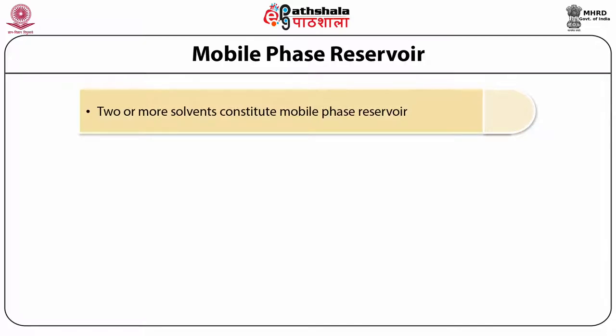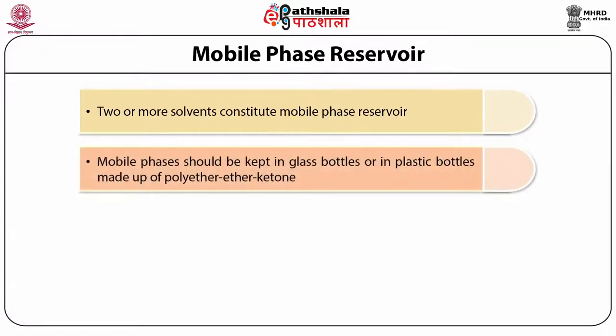Usually, most of the purification or separation in Ion Exchange Chromatography uses two to three mobile phases. These mobile phases are kept in glass bottles or in plastic bottles made up of polyether ether ketone, popularly known as PEEK. PEEK is used as it is chemically inert to most organic solvents. This is necessary as the mobile phases contain charged ions which may damage normal plastic bottles. Prior to using the mobile phase reservoir, degassing of solvents is very important. If it is not done, it may result in sharp spikes in the chromatogram.